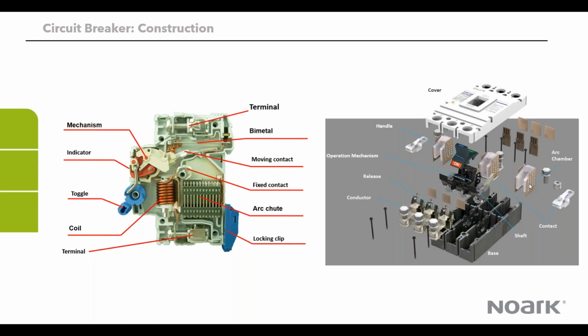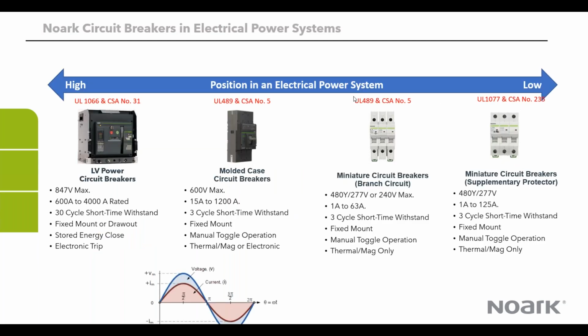So in the arc chamber, the breaker is able to break up the arc into smaller pieces and then dissipate them safely. In an abnormal situation, that process needs to be fast enough to contain the amount of arc that is being generated as a result of the trip. So that's an important component inside of the circuit breaker. So I'm going to move on to talk about the NOARK circuit breaker in the electrical system.